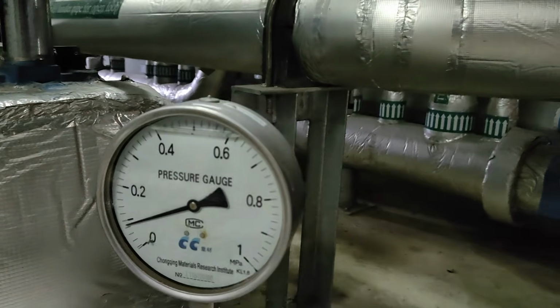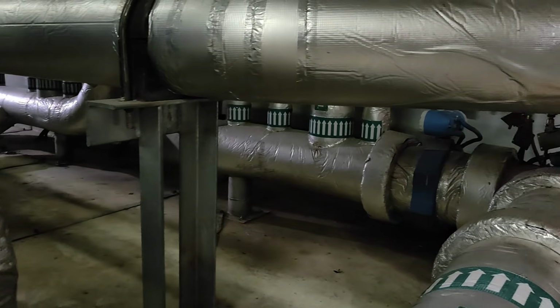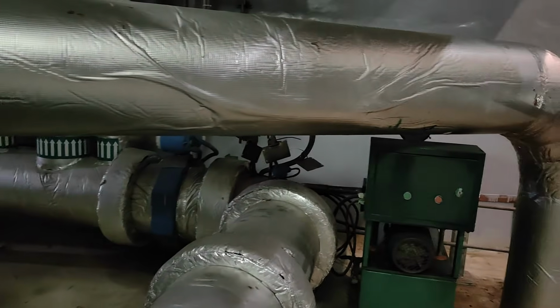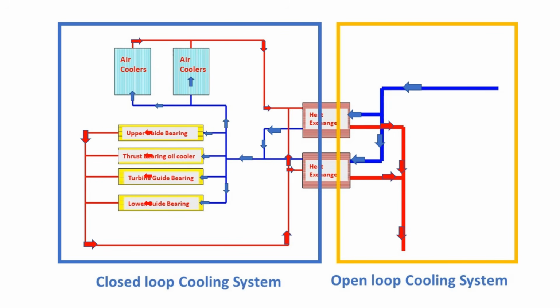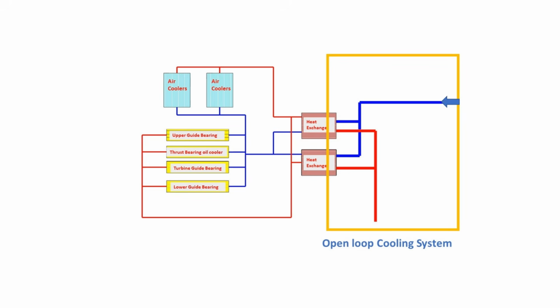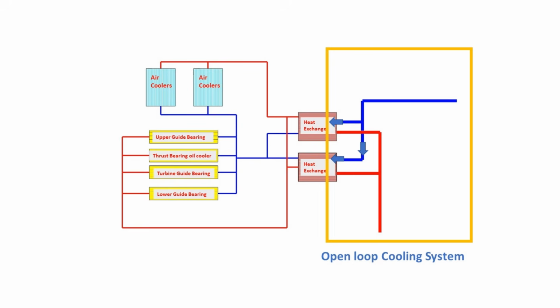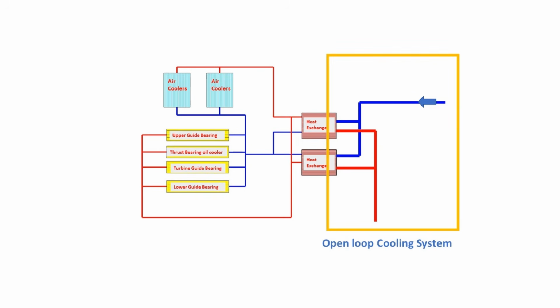So engineers created a genius solution. Instead of using one cooling system, hydropower plants use two completely separate water circuits, an open loop and a closed loop. So this is the secret behind the entire system. Okay, now, the open loop uses raw water or tailrace water. Its only job is to remove heat from the system. After absorbing heat, the water gets discharged back to the tailrace.